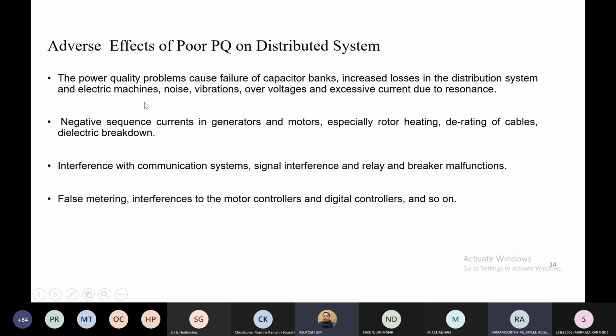This is the adverse effect of poor power quality on the distributed generation system. Power quality problems cause failure of capacitor banks. Capacitor banks are connected according to 50 hertz. If we supply multiple frequency components to the capacitor, its impedance will continuously vary, and there may be problems with the capacitor bank and adjacent inductors in terms of EMI and resonances.